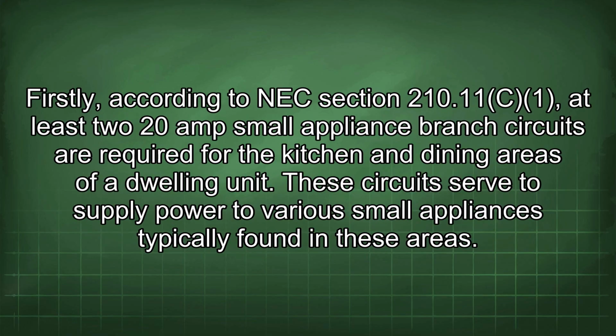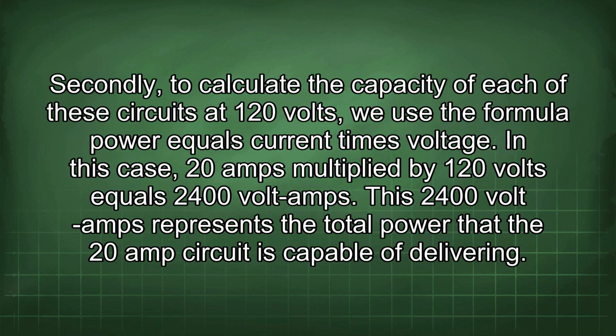Firstly, according to NEC section 210.11(C)(1), at least two 20 amp small appliance branch circuits are required for the kitchen and dining areas of a dwelling unit. These circuits serve to supply power to various small appliances typically found in these areas. Secondly, to calculate the capacity of each of these circuits at 120 volts, we use the formula power equals current times voltage. In this case, 20 amps multiplied by 120 volts equals 2400 volt amps. This 2400 volt amps represents the total power that the 20 amp circuit is capable of delivering.